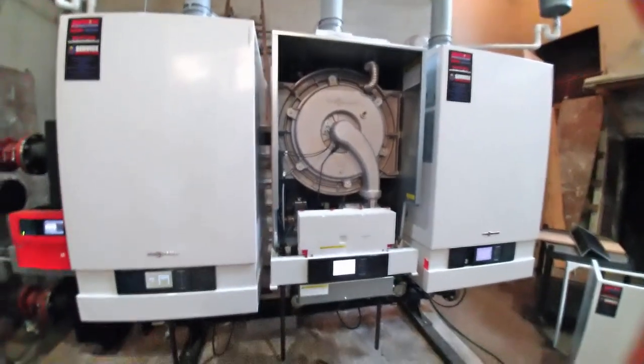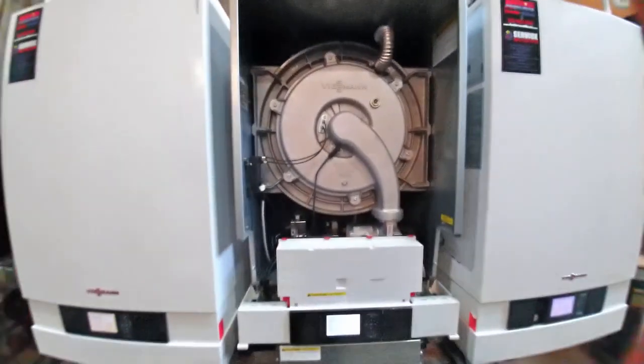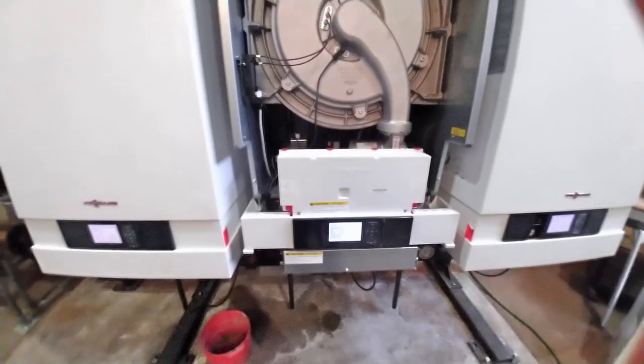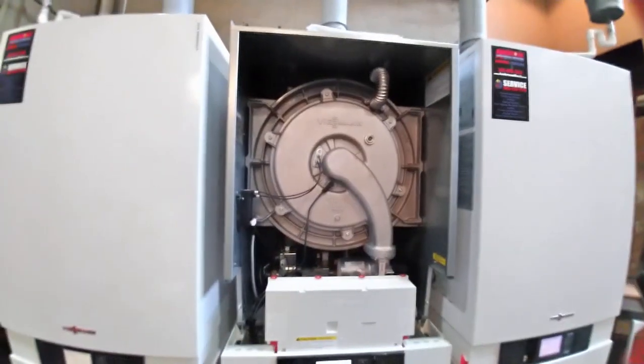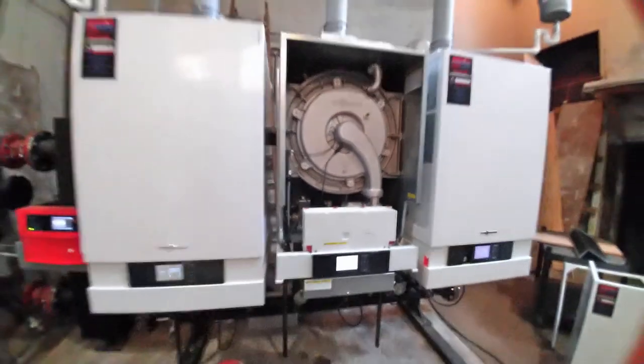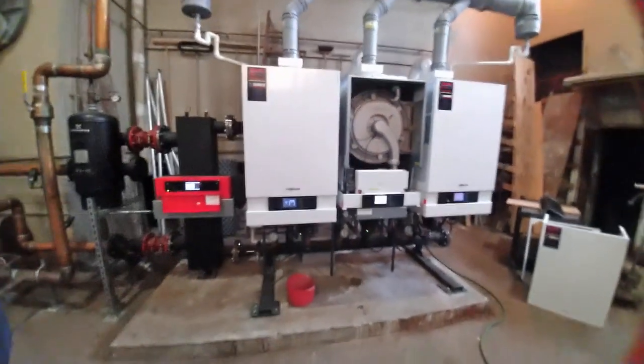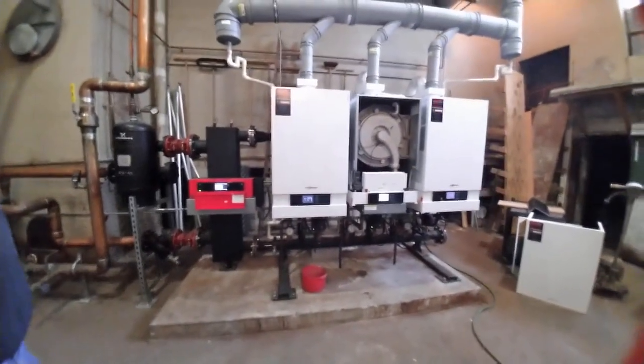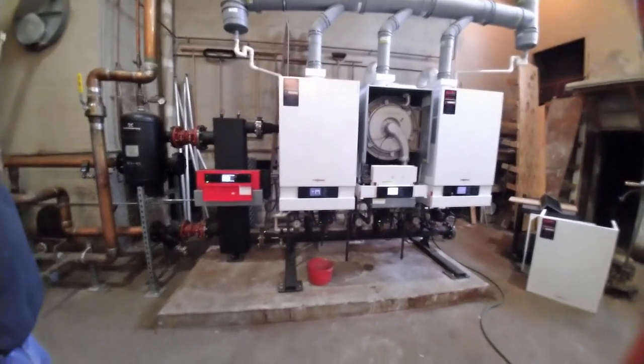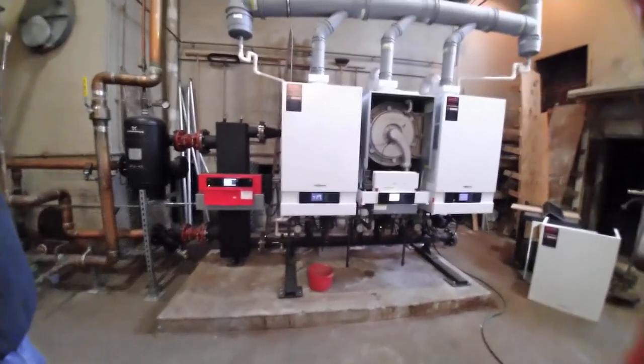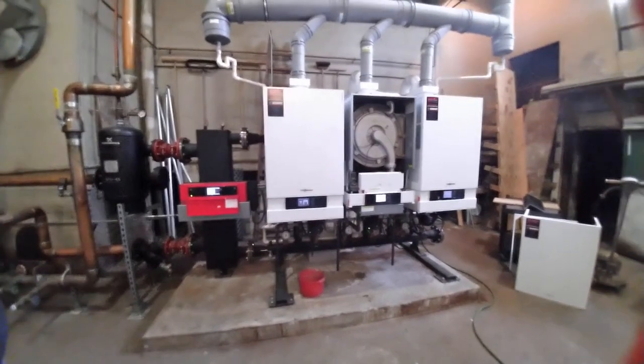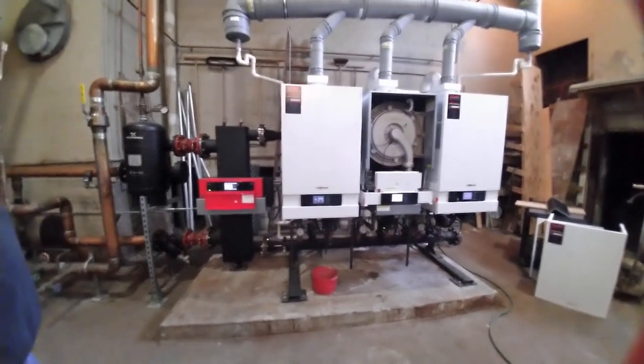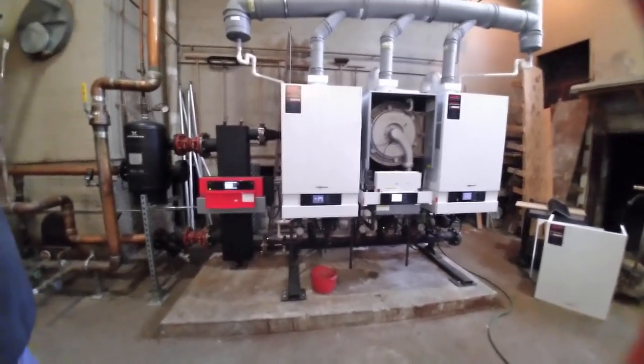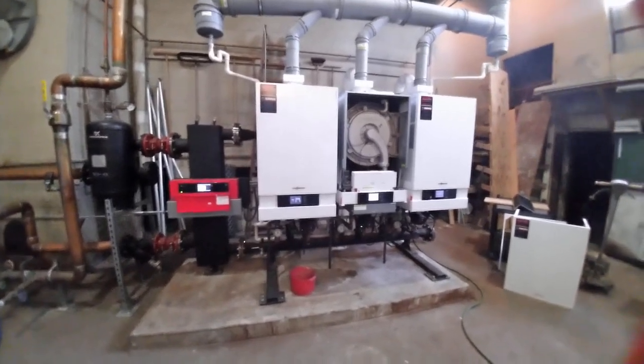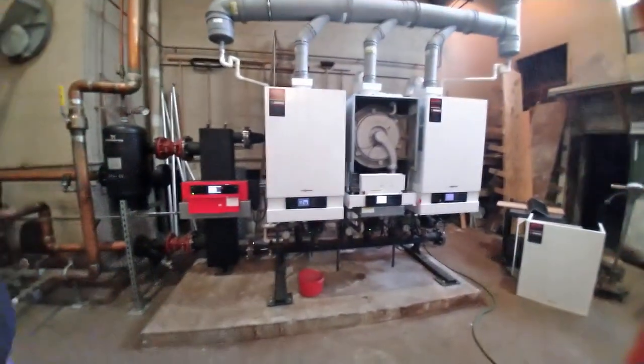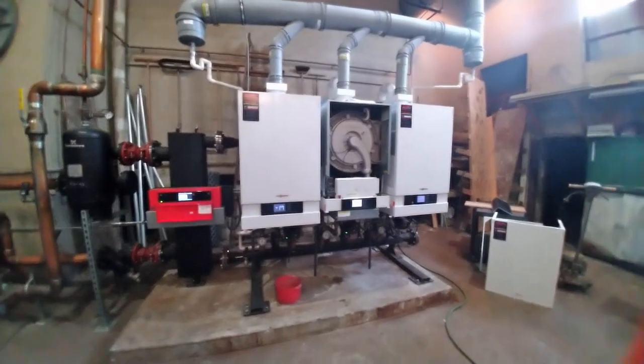So we've got it all back together. Turned it on. It's going through initial fire up right now, and the system really has been pretty incredible in this building. There was a 2.2 million BTU cast iron boiler that took up that whole concrete pad. We did some quick calculations based on actual gas consumptions and efficiencies and determined that we'd be more than adequate putting in 530,000 BTU high efficiency boilers.